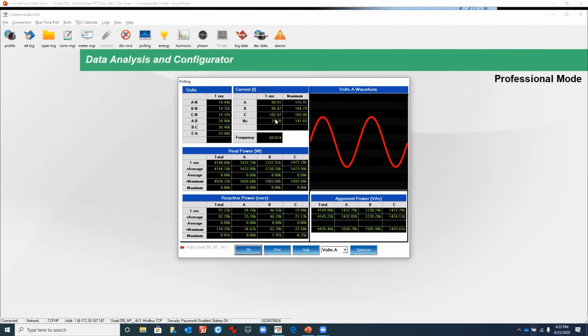So you can see there are some imbalances here, with some current flowing on the neutral, but this is very normal in a lot of cases. In the other column here, we see max and min values. Real power is demonstrated in the center of the screen, where you can see real-time megawatts, in this case 4,141K or 4.1 megawatts, and that would be the instantaneous demand value that you're seeing at that time. You also see average values and min and max values in the real power screen.